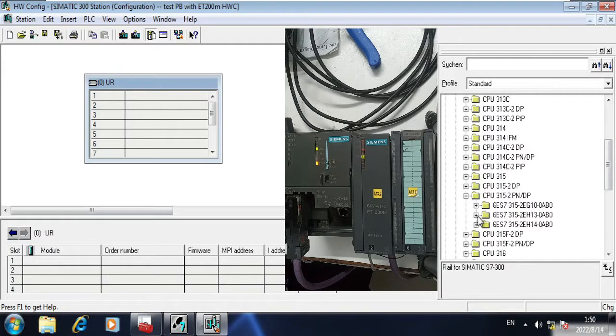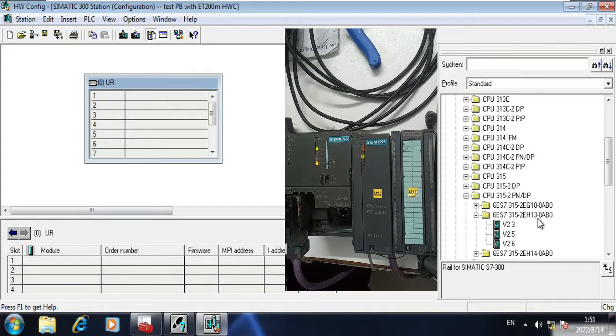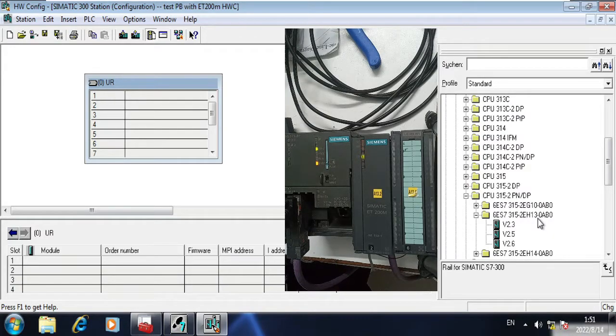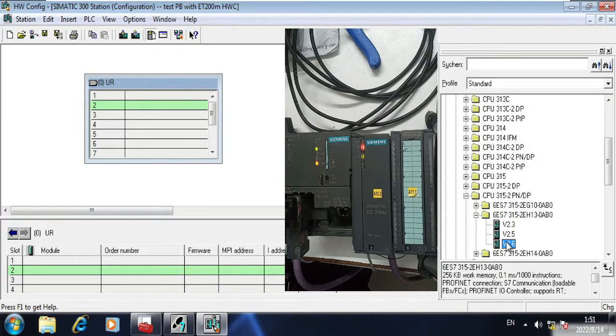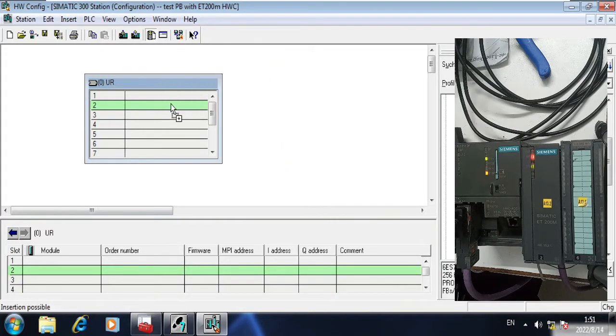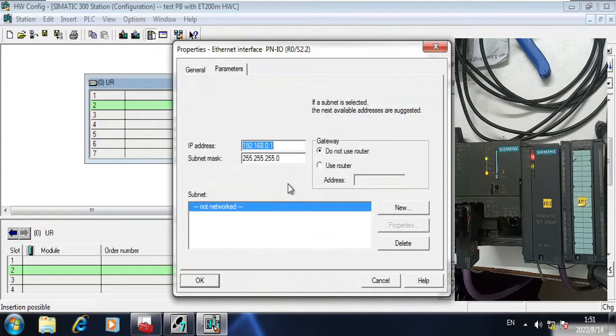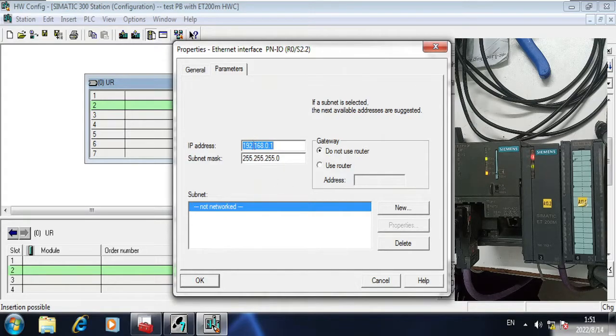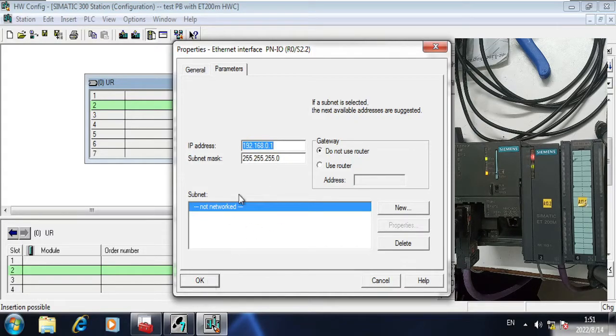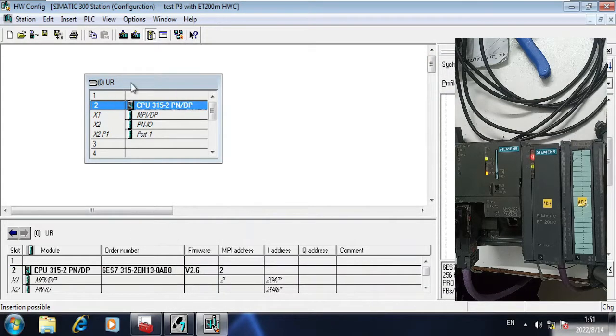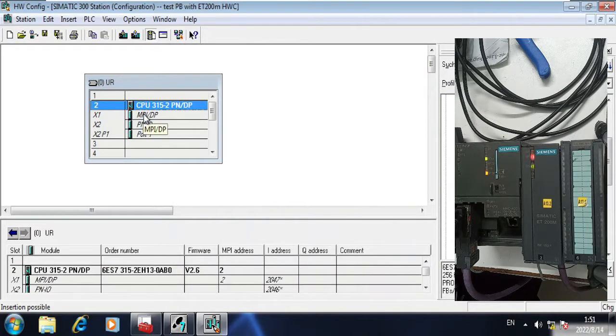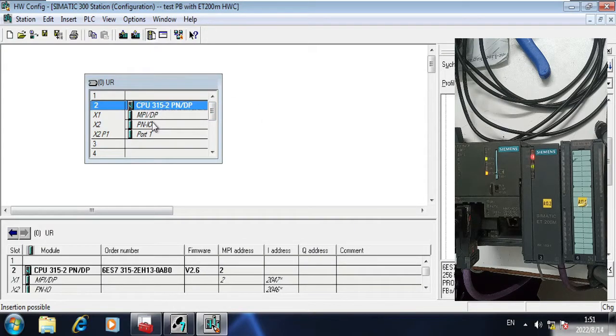Now I am using S7-300 CPU. This is 300 CPU and I am using 315-2PN/DP. I am using 315-2EH13. I have version 2.6, the 2.6 is written here. Click and drop it here. It is doing the standard procedure. As I have also one Ethernet port, I am 192.168.0.1 is my PLC IP address.